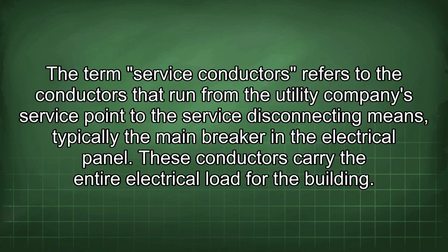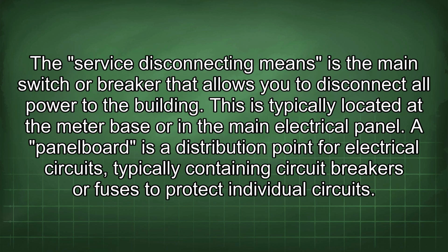The term service conductors refers to the conductors that run from the utility company's service point to the service disconnecting means, typically the main breaker in the electrical panel. These conductors carry the entire electrical load for the building. The service disconnecting means is the main switch or breaker that allows you to disconnect all power to the building. This is typically located at the meter base or in the main electrical panel.